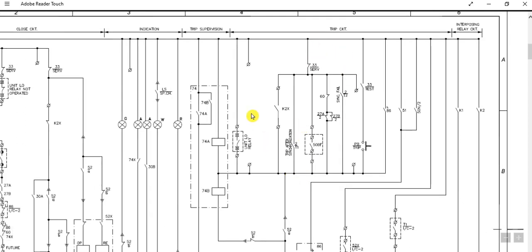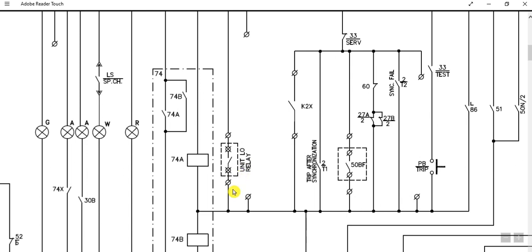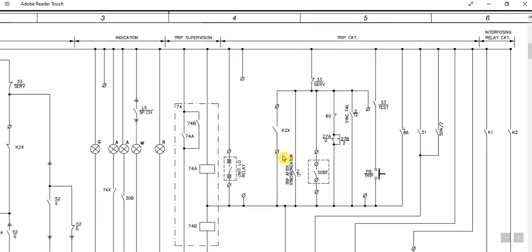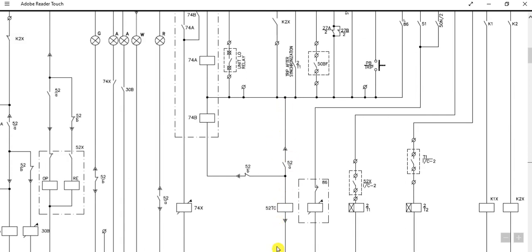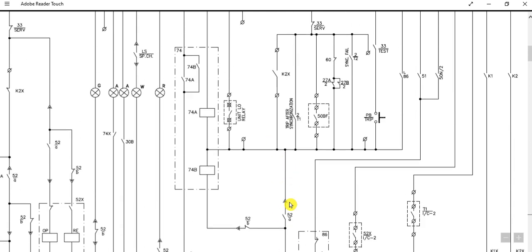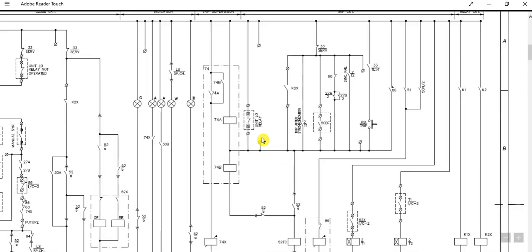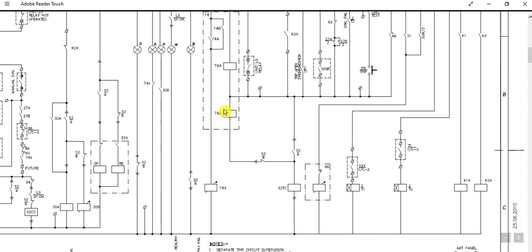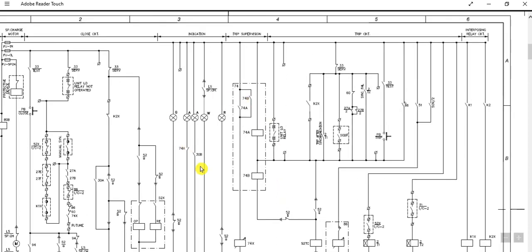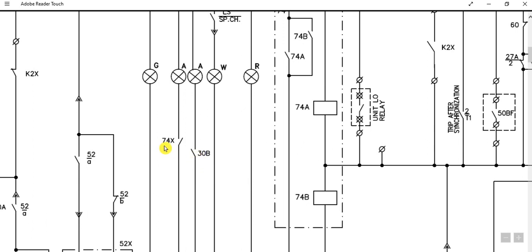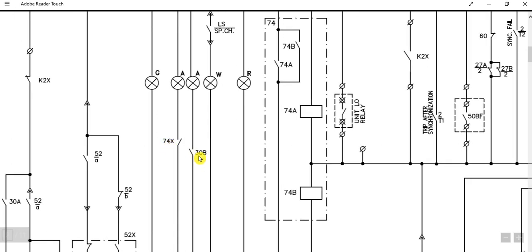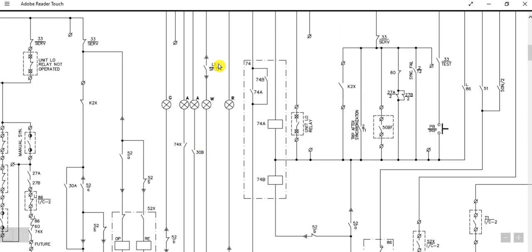Here is another path — this is the unit lockout relay. If it is operated, this path will be through and the circuit breaker will be tripped. Here, 74 is the trip circuit supervision relay. 74A and 74B contacts are also available through this trip circuit supervision relay — the circuit breaker may get tripped. With the help of auxiliary contacts from the trip circuit supervision relay, this 74X 30B, with the help of these auxiliary contacts and limit switch, these are the indication circuits.